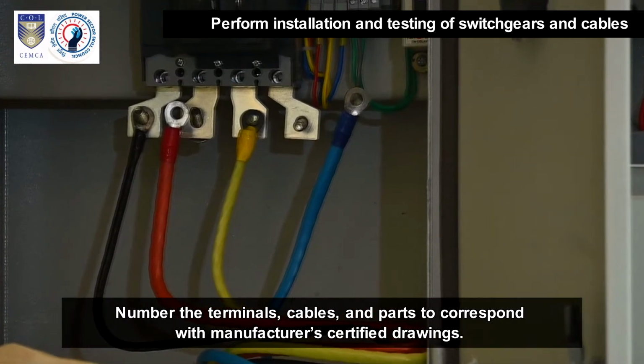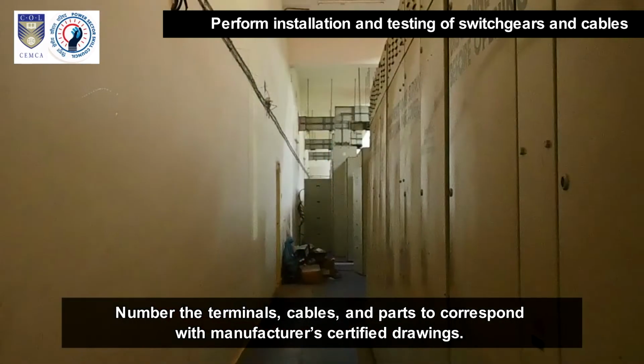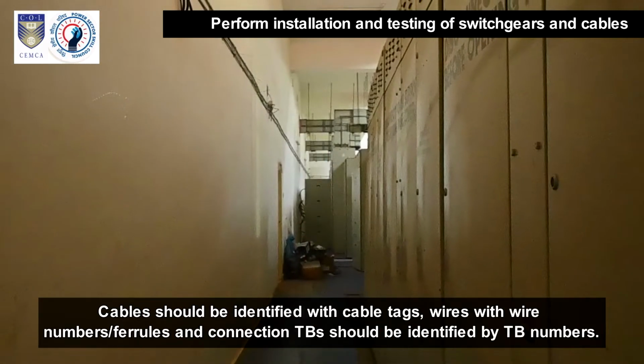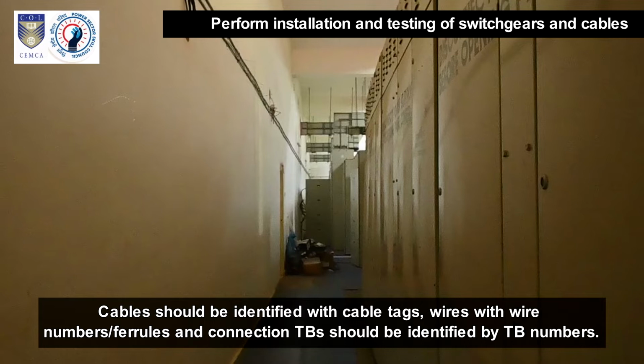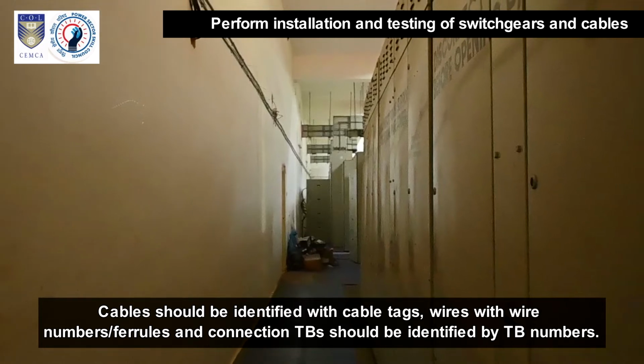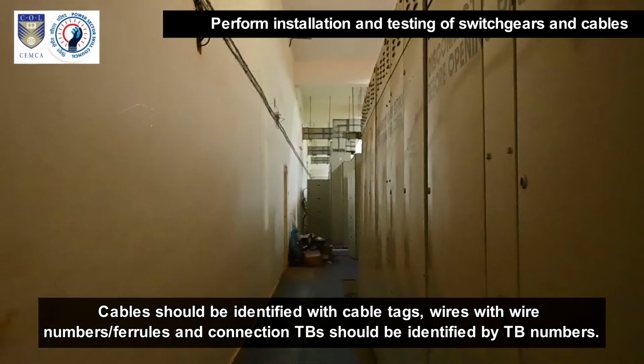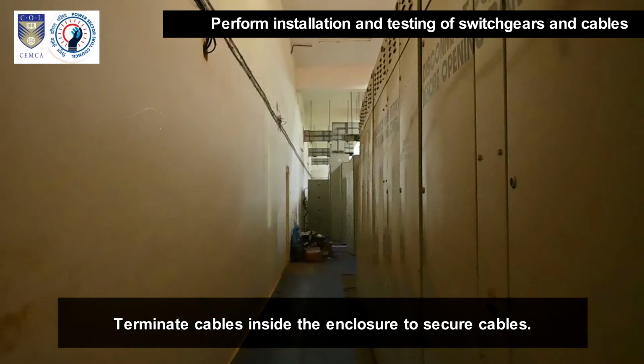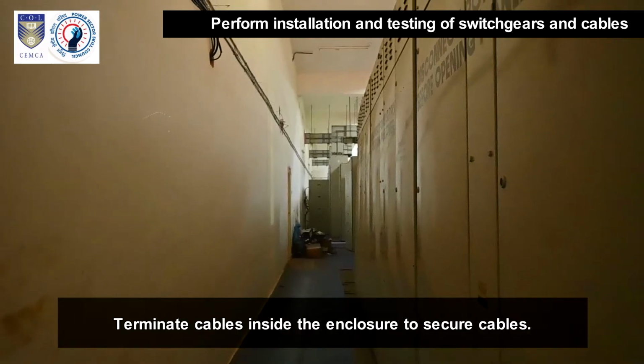Number the terminals, cables and parts to correspond with manufacturer's certified drawings. Cables should be identified with cable tags. Wires with wire numbers or ferrules and connection TBs should be identified by TB numbers. Terminate cables inside the enclosure to secure cables.